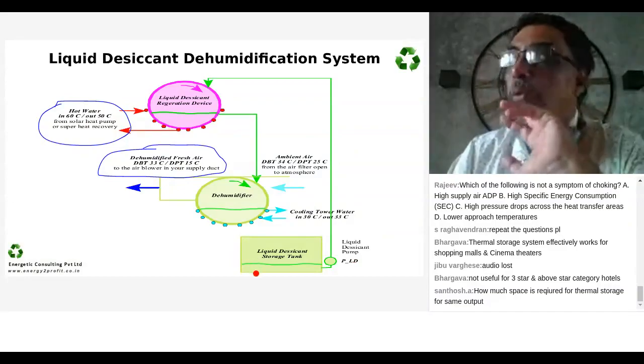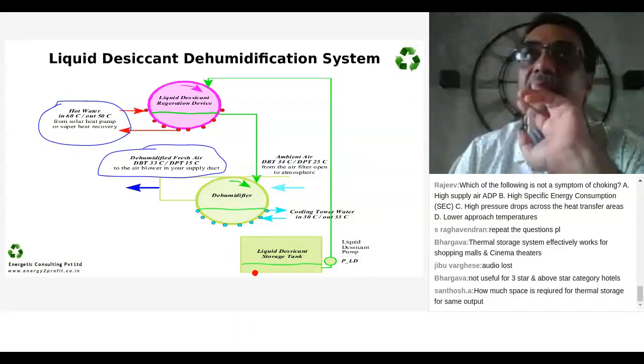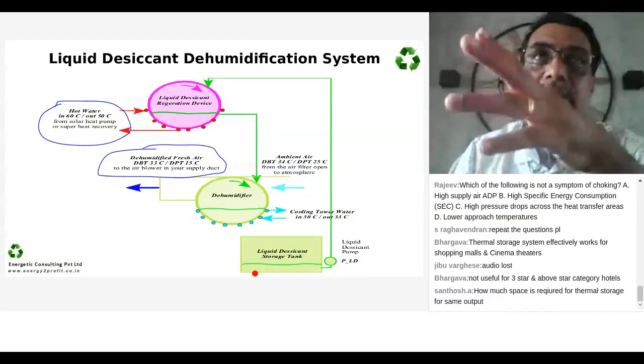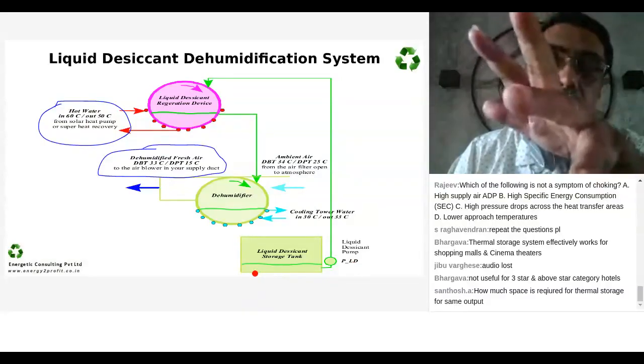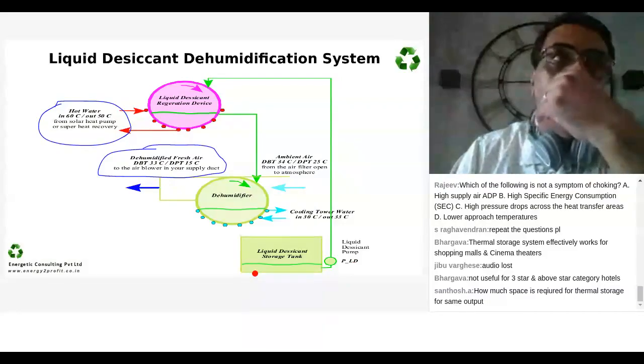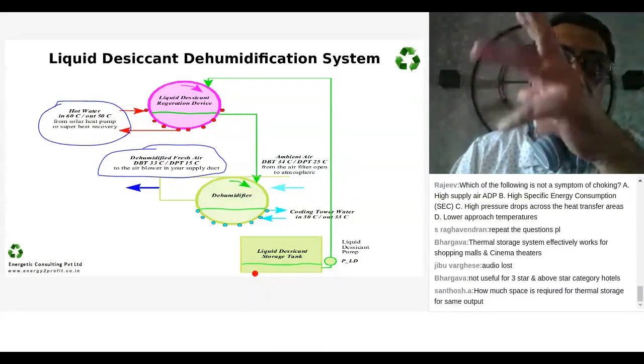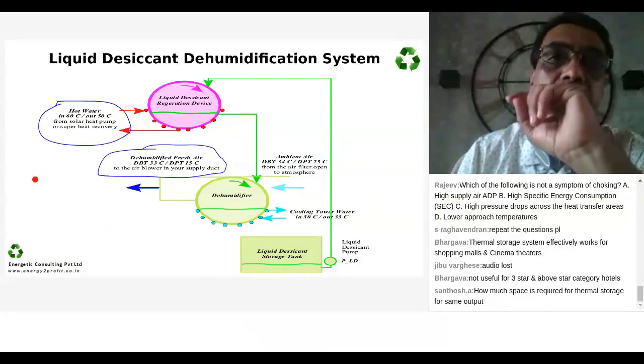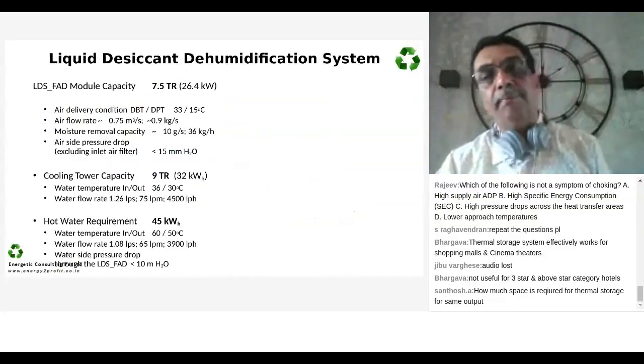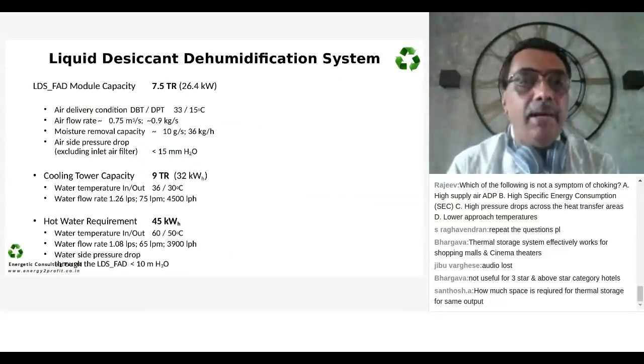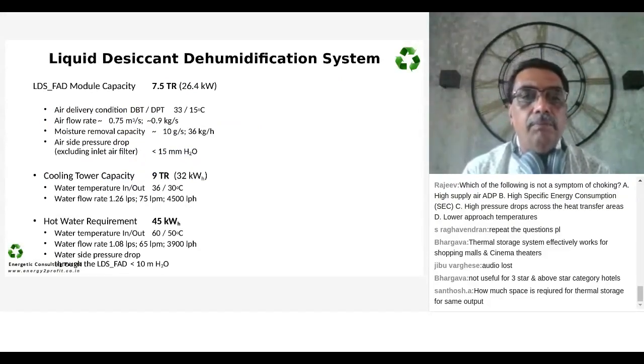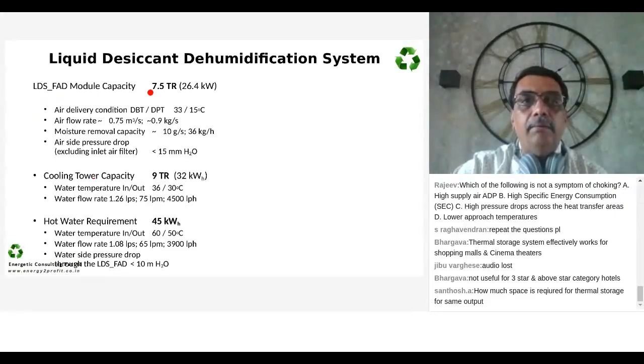So those of you who have a hospital or a healthcare facility and are facing a challenge of large energy consumption, or you want to make your facility COVID compliant, and energy or transformer sizing is coming out to be a constraint, this is a very good solution. How does it operate? These are the economics of it. The entire system needed 32 kilowatt of cooling water and 45 kilowatt of hot water. So this was the whole system.